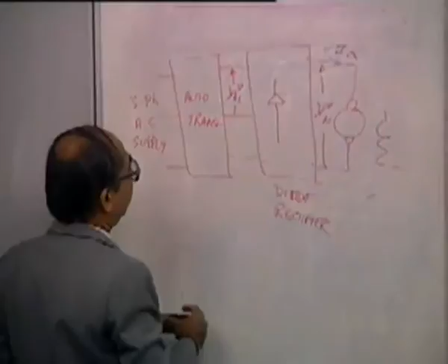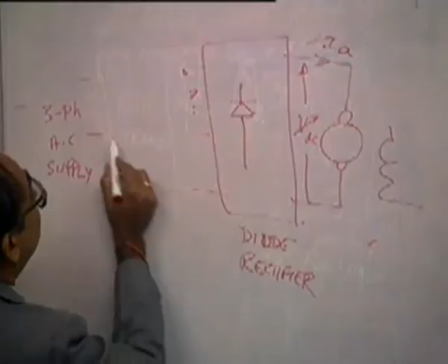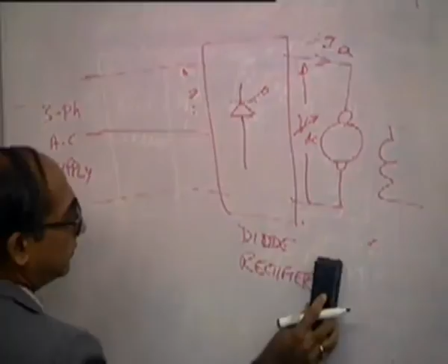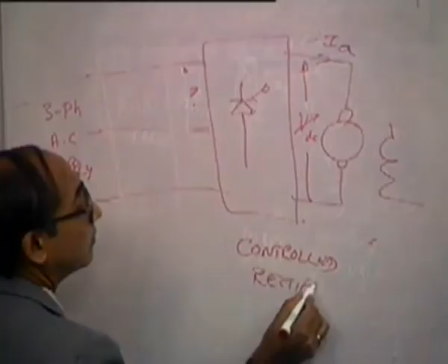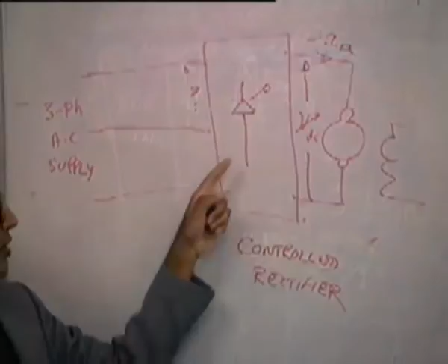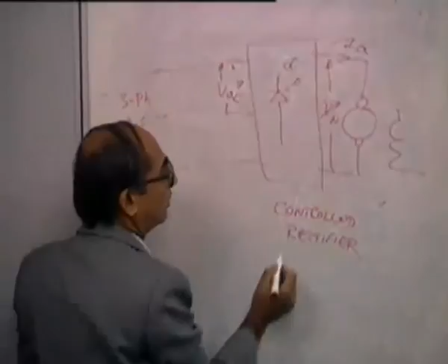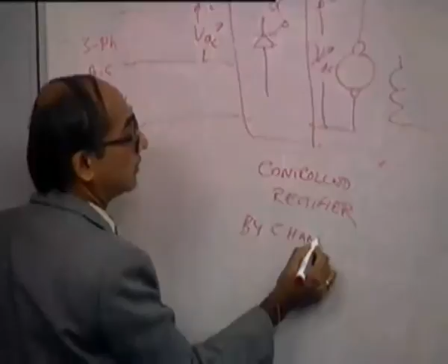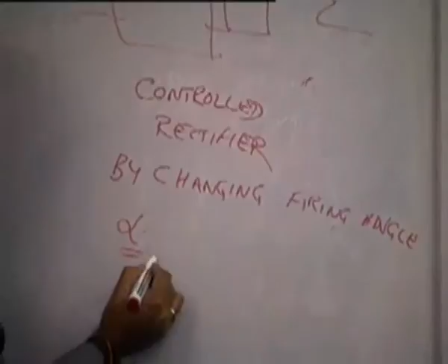Another variation of this is, instead of an auto transformer and a rectifier bridge, diode bridge, you can have a controlled rectifier, thyristors. This is again present day. Presently, this is one of the methods of changing the voltage here. So with a fixed AC here, you get a variable DC because of the firing angle control. So here, by changing the firing angle alpha, VDC can be changed.